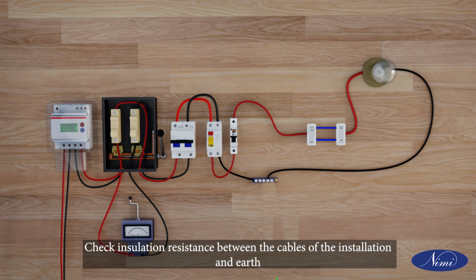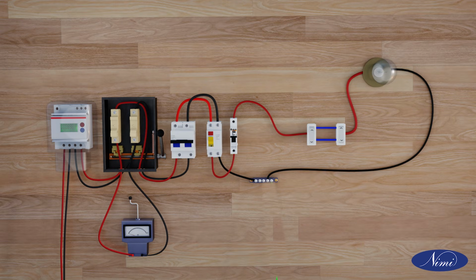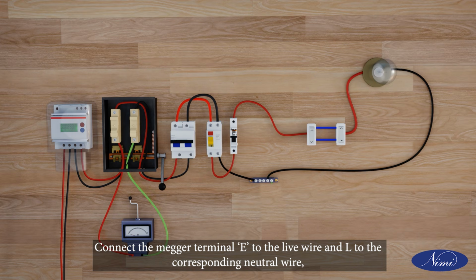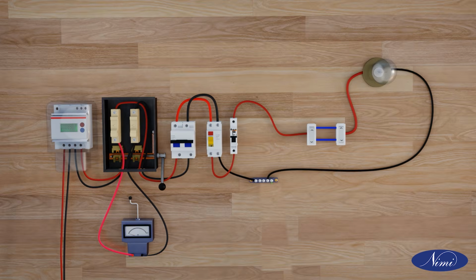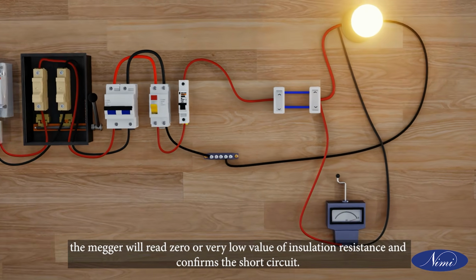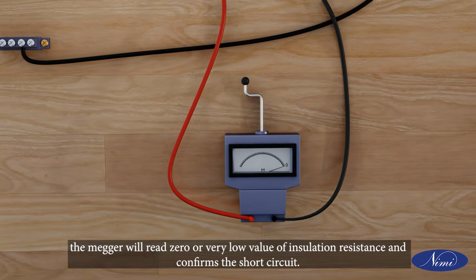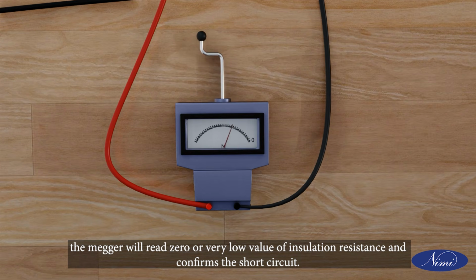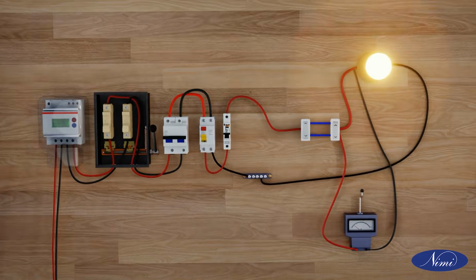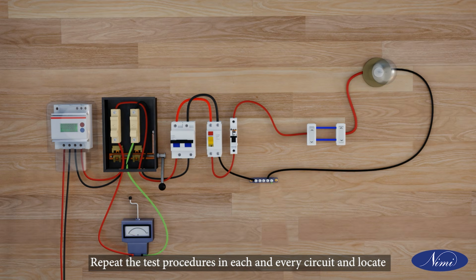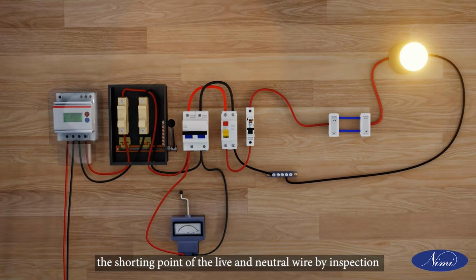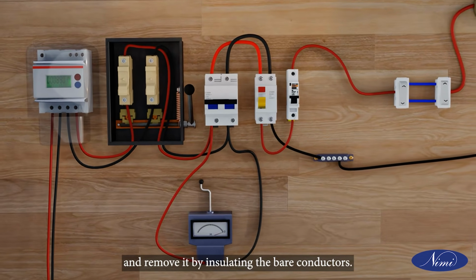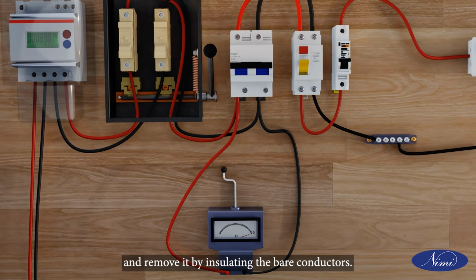Check insulation resistance between the cables of the installation and earth. Connect the megger terminal E to the live wire and L to the corresponding neutral wire. The megger will read 0 or a very low value of insulation resistance and confirms the short circuit. Repeat the test procedures in each and every circuit and locate the shorting point of the live and neutral wire by inspection, and remove it by insulating the bare conductors.